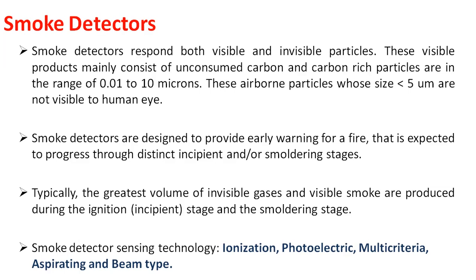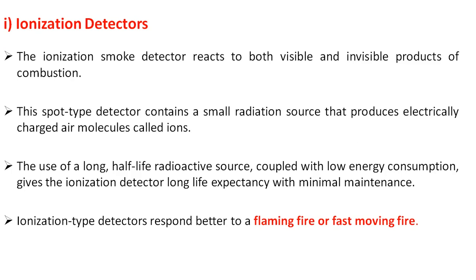The greatest volume of invisible gases and visible smoke are produced during the incipient and smoldering stages, and smoke detectors are best suited for these stages. The first type is the ionization detector, which reacts to both visible and invisible products of combustion. This ionization type detector contains a small radiation source — Americium-241 — which emits alpha particles. These alpha particles ionize the air and produce ions and electrons, which are measured by an electrode proportional to the ion current.